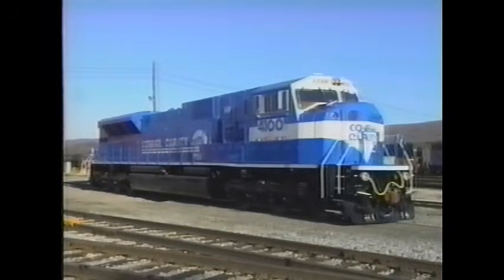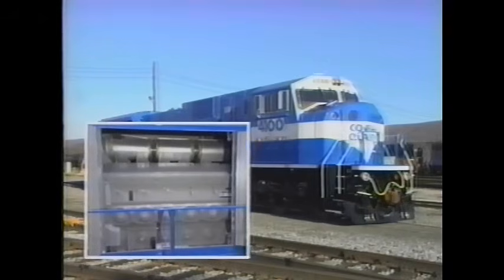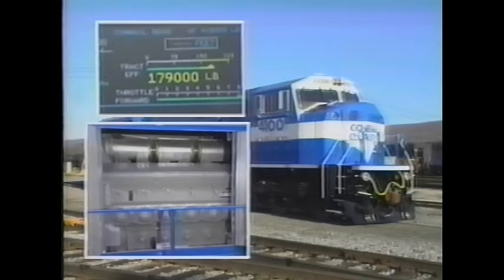First off, the SD80MAC has greater capabilities than anything you've ever handled, especially below 10 miles per hour. The 80MAC produces 5,000 horsepower and 185,000 pounds of starting tractive effort. The best our most powerful DC locomotives can achieve is 108,000 pounds of tractive effort, and that's at 11 miles per hour. Below that speed, higher tractive effort is possible. However, the thermal limits, or short time ratings, of the DC traction motors and higher wheel slip potential limit the amount of TE you can actually apply.